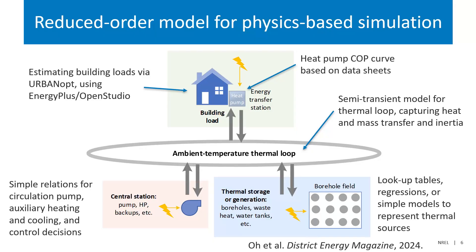On the reduced order side, this is for capturing the physics of what's actually happening on the loop: where is heat moving over time, where is water moving, and how much electricity is being used for that whole process. The main backbone of this model is the ambient temperature loop. A lot of the modeling effort goes into capturing how heat moves physically around this loop, how much thermal inertia is in there — so if you dump in some heat, how quickly it changes temperature and propagates around the loop affecting all customers.